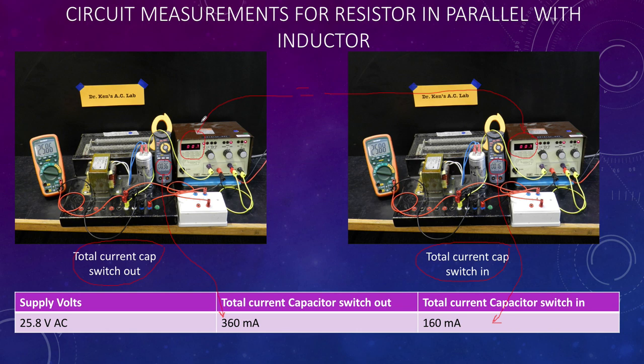Because the power hasn't changed, that's an important aspect of power factor correction. We've reduced the current, but we haven't reduced the amount of power that the installation is drawing. In this case the power is the internal resistance of our inductor representative, representing our motor.